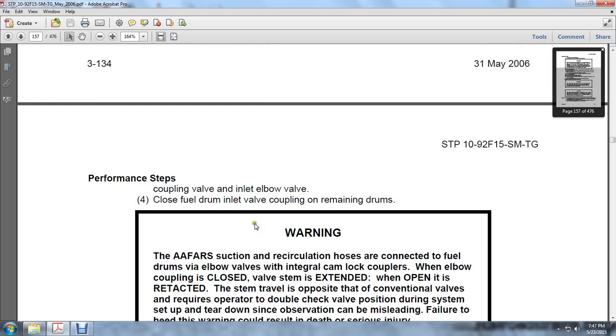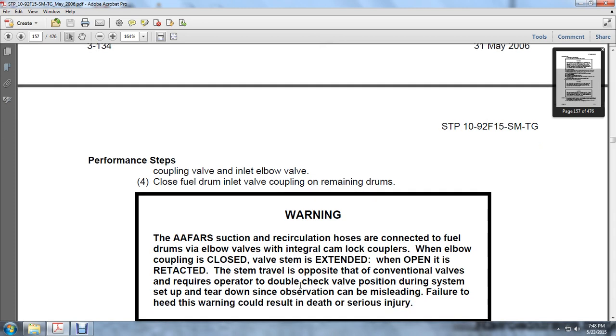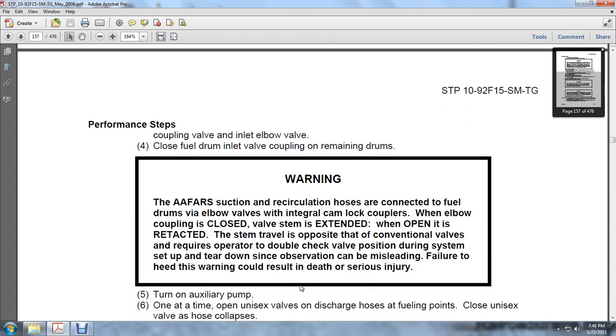At the advanced aviation forward area refueling system, suction and recirculation hoses are connected to the fuel drums via elbow valves, with integral cam lock couplers. When the elbow coupling is closed, the valve stem is extended. When the coupling is retracted, the valve is open. This is the opposite of conventional valves. The operator must double check the valve position during system setup and tear down, since the observation can be misleading. Failure to heed this warning could result in death or serious injury.